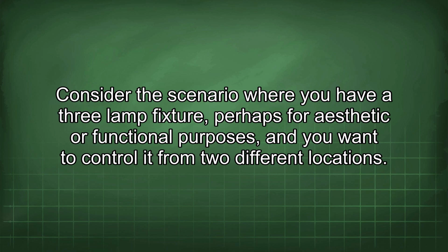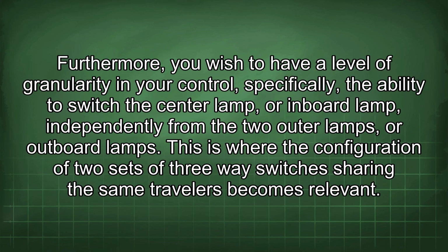Consider the scenario where you have a 3-lamp fixture, perhaps for aesthetic or functional purposes, and you want to control it from 2 different locations. Furthermore, you wish to have a level of granularity in your control, specifically the ability to switch the center lamp or inboard lamp independently from the 2 outer lamps or outboard lamps. This is where the configuration of 2 sets of three-way switches sharing the same travelers becomes relevant.